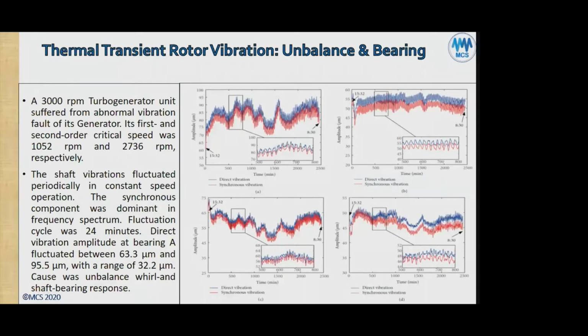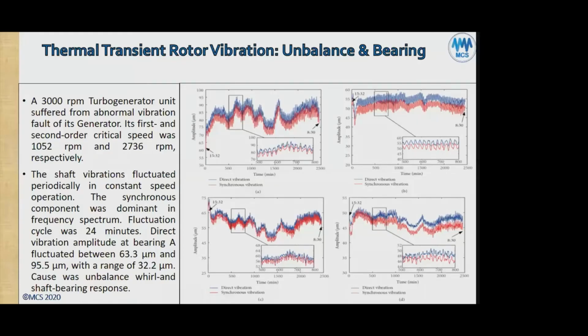Next example, we only have 2 more slides and we're done, gentlemen. Here we have a thermal transient: a 3000 RPM turbo generator unit suffered from abnormal vibration fault of its generator. These are the 2 bearings of the generator: A, B are one bearing, X and Y, and C and D are the second bearing, X and Y. This is the vibration showing direct overall vibration and synchronous vibration in red color, and you're showing the amplitude with time.